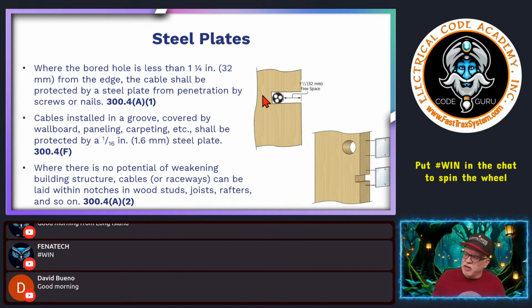Now, you are allowed to do it in notches as well, but you still have to have that separation. Of course, if that framing member has something going on, you wouldn't need a plate as long as you can have that spacing. I don't know why you would do this, since it pretty much compromises the framing member, but I'll leave that to the building guys, we'll let the building inspector harp on you for that. This is no different than boring the hole right in the middle, but it does affect the integrity. If you're less than 1.25 inches, like this one here, for whatever reason, then there's a nail plate. And if you do a small notch, you can use a nail plate too. Anything less than 1.25 inches from the edge of the framing member to the edge of the board or a notched opening needs that protection.